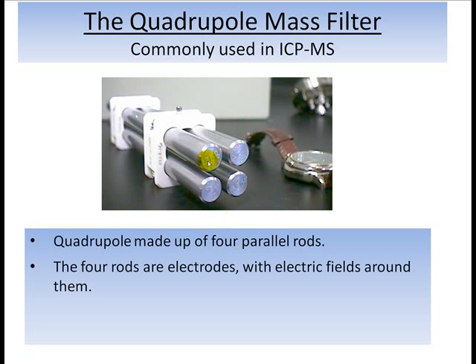So the quadrupole mass filter has an anatomy, or physical layout, that looks a bit like this. There's four parallel rods. Rods are actually electrodes. They have electric voltages applied to them, and then because of those voltages, there's electric fields that go out in space around them.